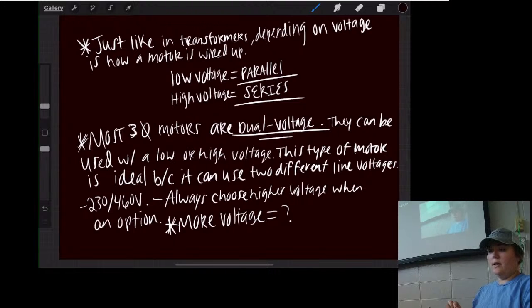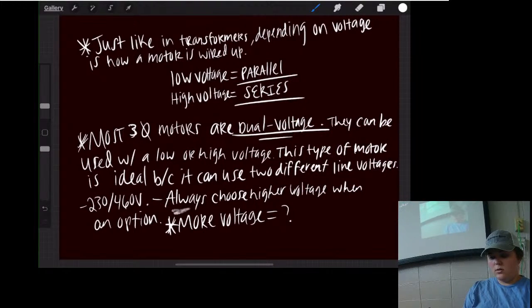Most three-phase motors are dual voltage, and they can be used with a lower or higher voltage. That type of motor is ideal because it can use two different line voltages - if you've got 240 or 480 or whatever. The example in the book was 230 to 460, but I think it's easier to just say 240 to 480 because that's what we're used to dealing with. And on a dual voltage motor, you always want to choose that higher voltage when it's an option.